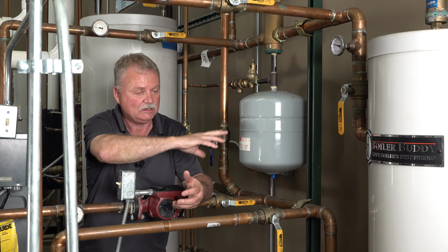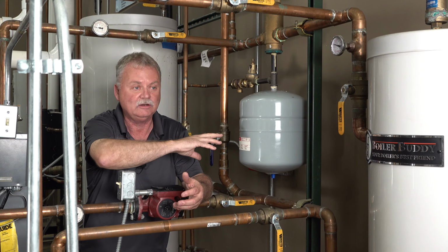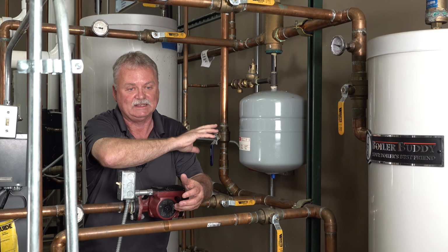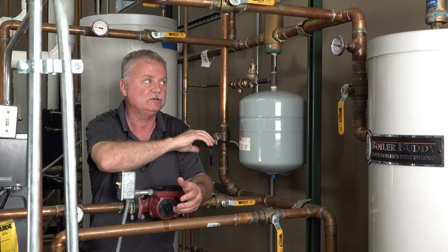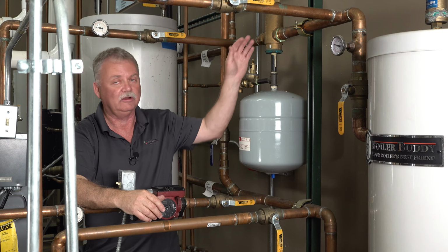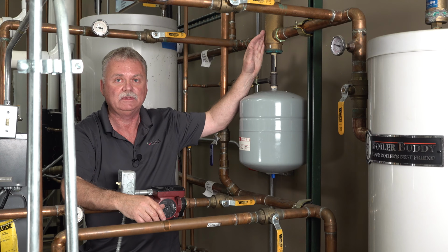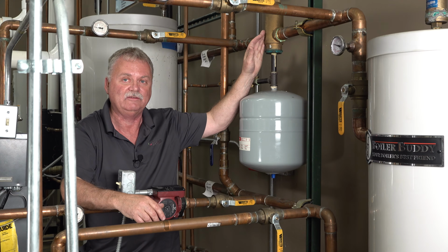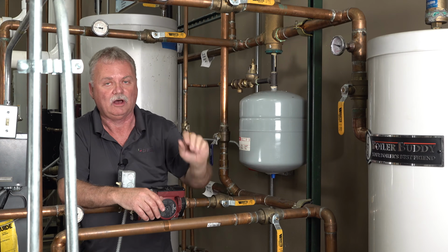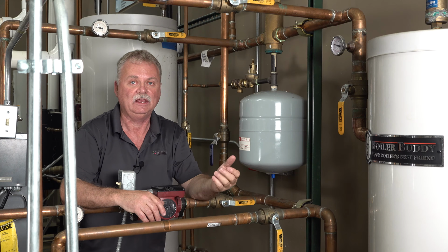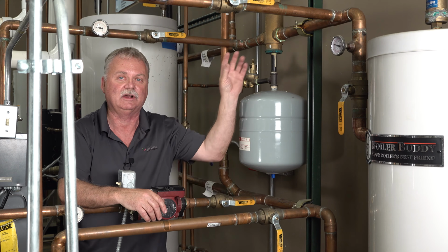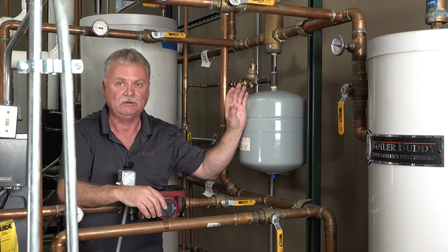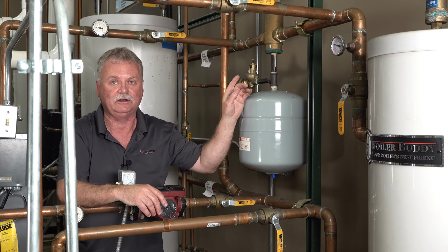Expansion tank, like we talked about, an expansion system sits down here. Normally, it's at the hottest point of the boiler leaving water temperature, because at that point, the air eliminator can do its best job. Hotter the water, the more air we get out of it. Also, if the air eliminator is on the intake side or the inlet side of the circulator, it's at the lowest pressure. So that again makes my bubbles as large as possible. But again, I have a whole separate video on that air eliminator.